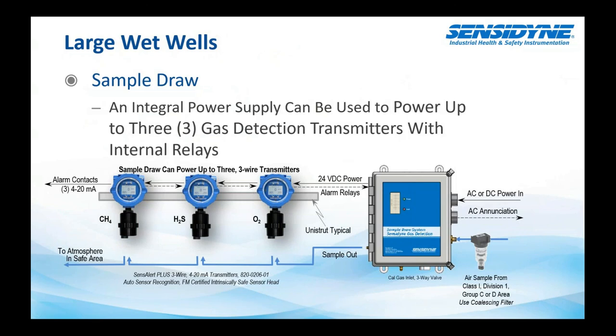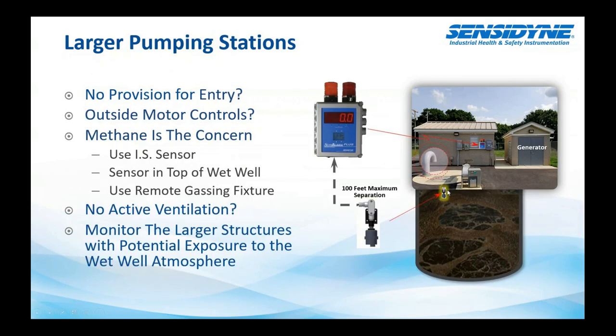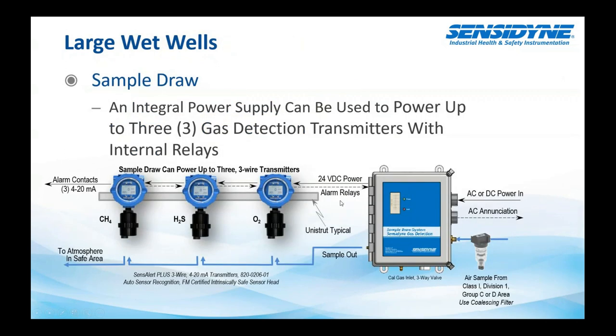Another way to monitor these using the same transmitters, but without having the sensor present in the well, is the sample draw system. This gives us the ability not only to not have these sensors down in that nasty environment, but we can pull a sample from the environment, use a coalescer filter to filter the gas as it comes in, and remove the moisture from it. That also gives our sensors the ability to have a longer life because we're not exposing them to a lot of moisture, which could cause the life of the sensor to degrade. And then we can monitor for multiple gases in one area. So we can have one tap going into the well, coming through the sample draw system, passing that gas across these three sensors and getting your alarm relays out of these three sensors. You can see which gas is alarming by the faceplate, which will tell you the PPM levels or LEL levels of the gas that it's alarming on or sensing. And then you would vent that to the atmosphere, obviously in a safe location.